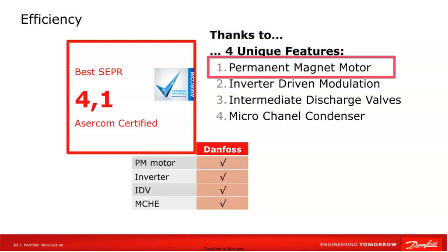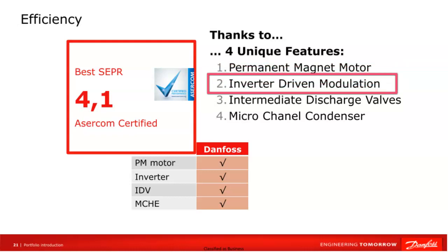Permanent magnet motor. This is one of the main factors. A motor using permanent magnets is more efficient and durable, which translates into lower energy consumption. Inverter modulation. The Optyma inverter condensing unit uses inverter modulation, which means it can adjust its capacity depending on the current needs, which is a significant factor in energy saving.